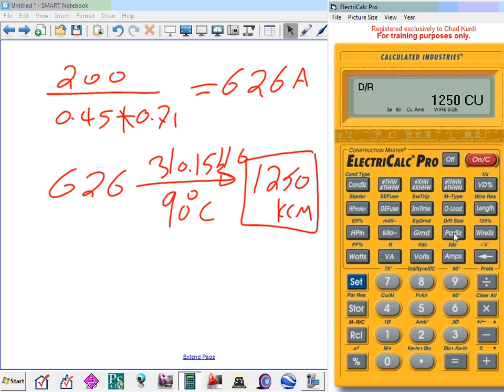To compute the conduit size, you have to switch. You have to give it the conduit; we'll do that conduit in a second here. What are you going to do for that 1250? You're not going to find a conduit for that size. Guaranteed, 3, 4 of them. You're not going to find a conduit. But if it's 4-aught, you can.